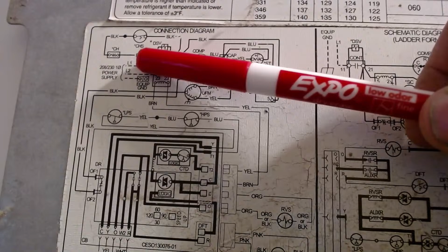First thing we come to is a crankcase heater, to a crankcase heater temperature switch, and then back down to 21. So what's happening is that switch is sensing the temperature of the discharge line, and it says, "Hey, I'm up and running. You can stop the crankcase heater," and it opens that crankcase heater. It opens on a rise. All right. So let's continue with the 21.